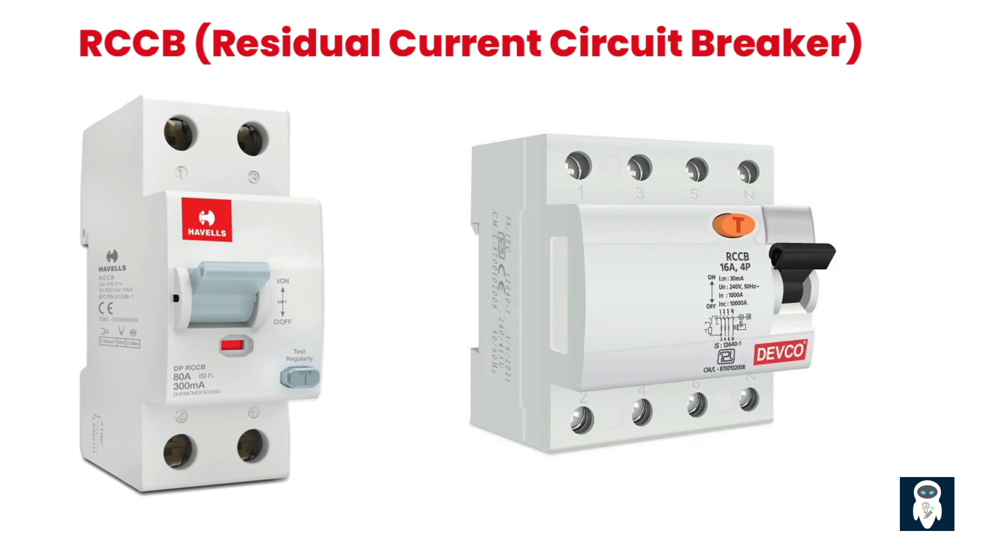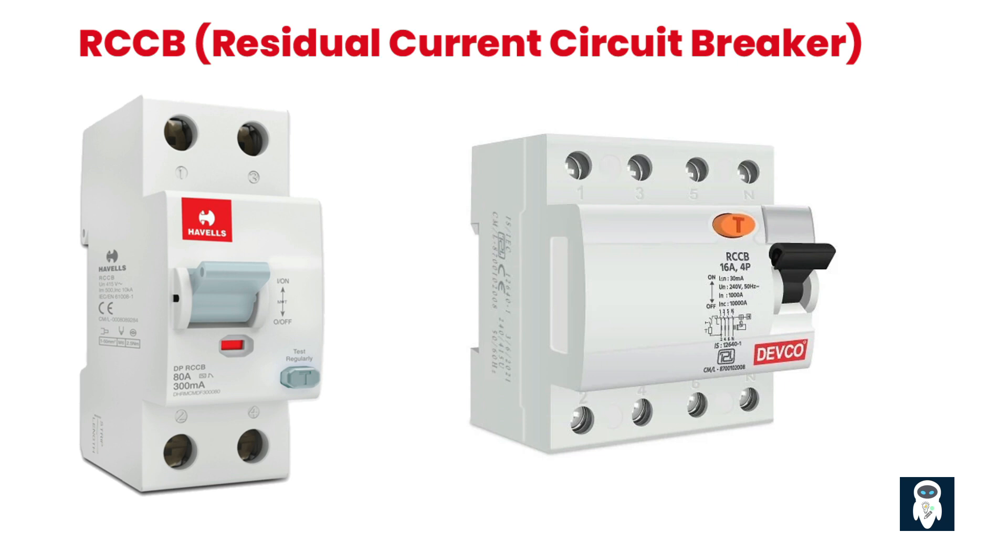If the RCCB detects a significant imbalance, it quickly disconnects the circuit, preventing electric shock or fire hazards. RCCBs work based on the principle of residual current, which refers to the difference in current between the live and neutral conductors. Normally, the current flowing through the live and neutral conductors should be equal. However, in the case of a fault, such as a person coming into contact with an exposed live wire or a damaged appliance causing leakage, a portion of the current may flow through an unintended path, such as the ground or the person's body. This creates an imbalance in the current, which is detected by the RCCB.